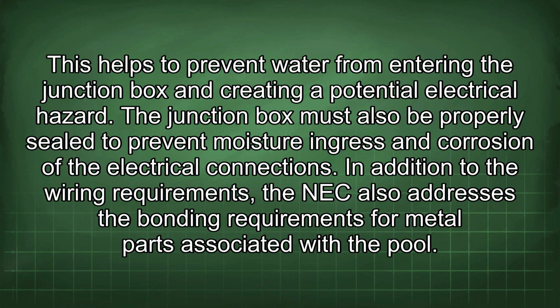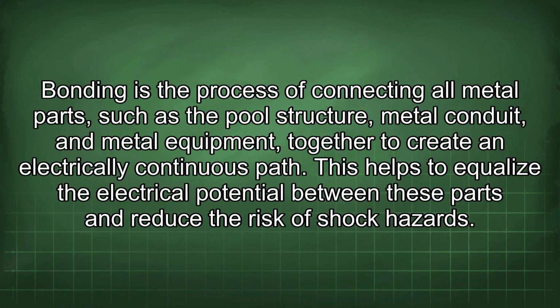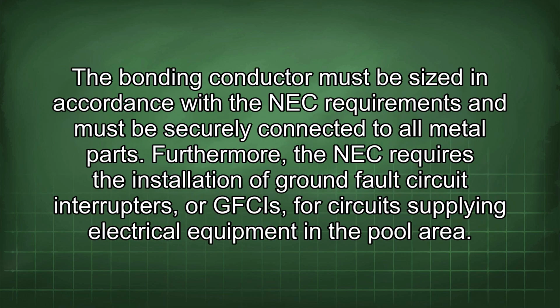In addition to the wiring requirements, the NEC also addresses the bonding requirements for metal parts associated with the pool. Bonding is the process of connecting all metal parts, such as the pool structure, metal conduit, and metal equipment, together to create an electrically continuous path. This helps to equalize the electrical potential between these parts and reduce the risk of shock hazards. The bonding conductor must be sized in accordance with the NEC requirements and must be securely connected to all metal parts.